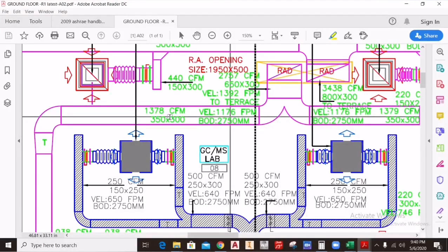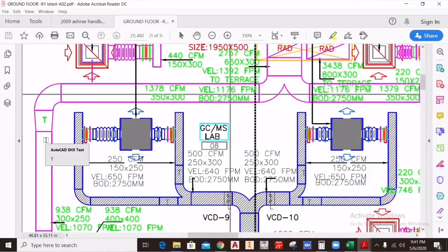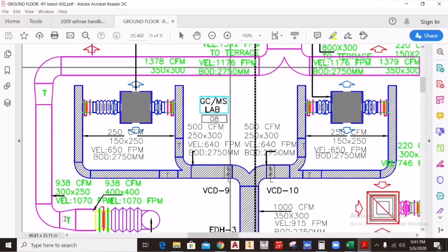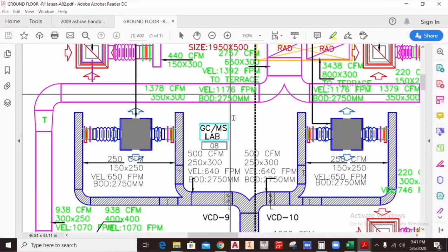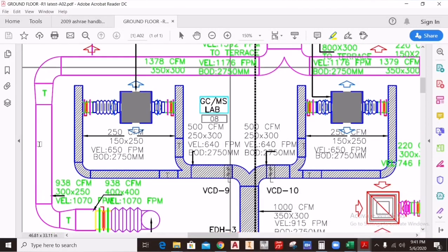What is external static pressure? External static pressure is the pressure that is used to overcome the pressure losses in your duct system. As you can see, there is a return air duct with a mouthpiece, a straight duct, an elbow, and a transition — all of which have some pressure losses. There is also a reducer, flexible duct, volume control damper, filters, and other accessories. All of these are obstructions in the path of airflow, and all obstructions create some pressure loss.